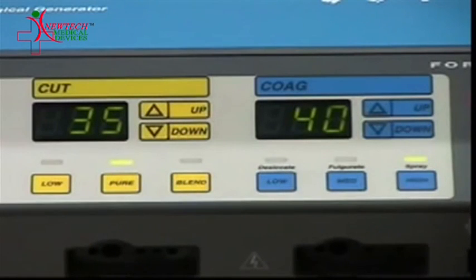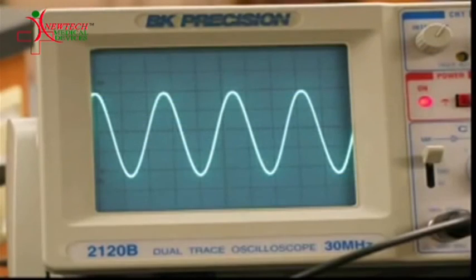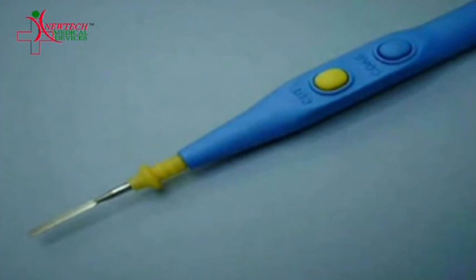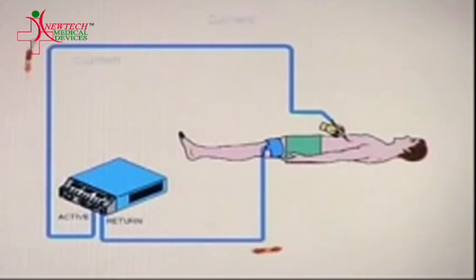One voltage divider network and an electrosurgical generator are necessary for this device to work. The pencil also includes at least one activation switch supported on the housing which is configured and adapted to complete a control loop.